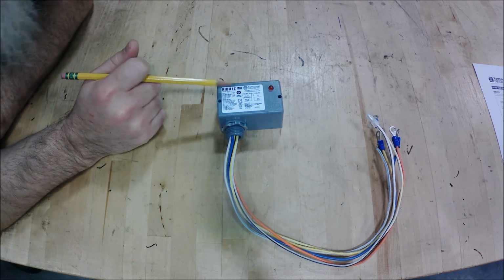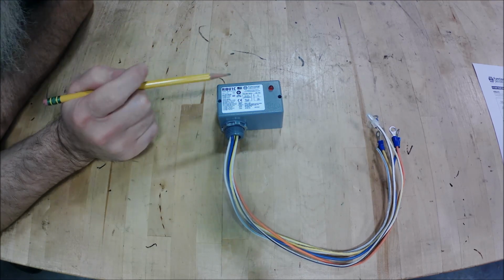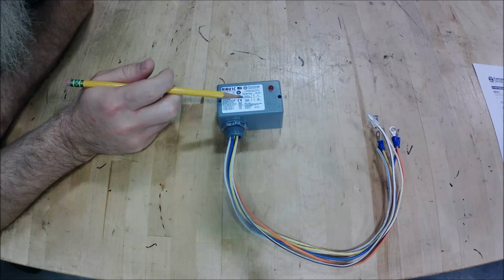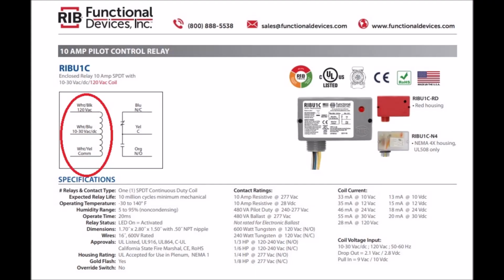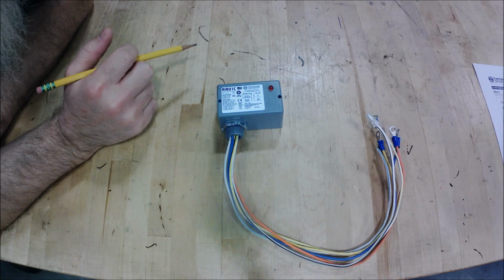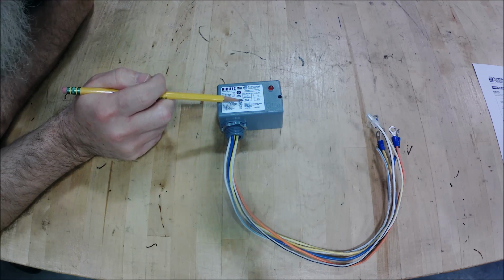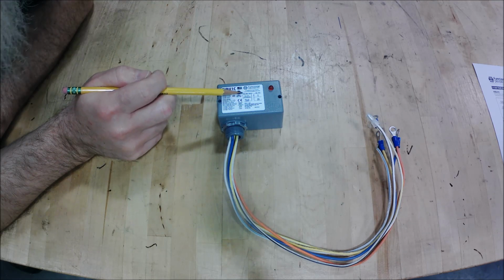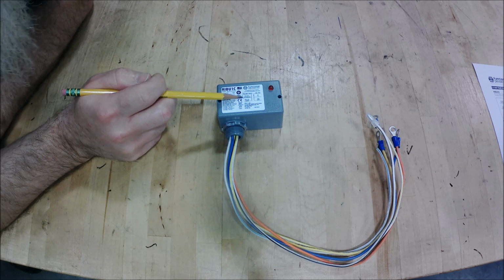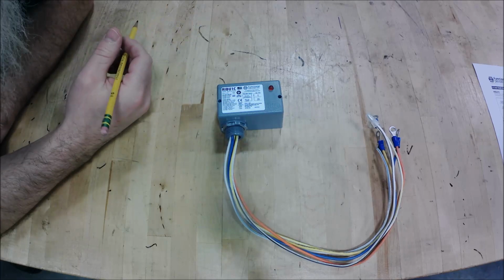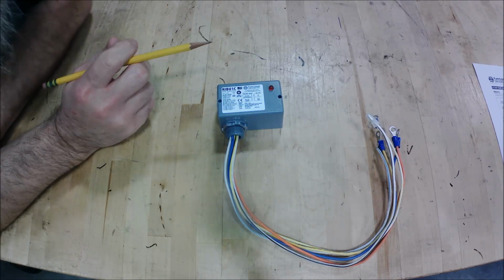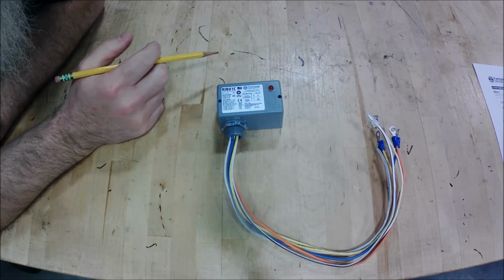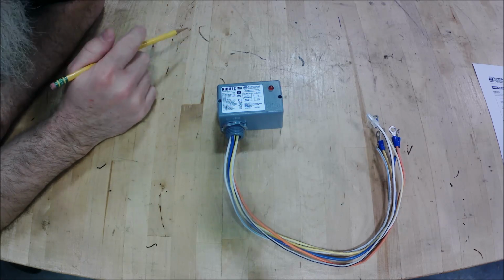So on top of it, and I'll throw up the spec sheet real quick, you've got your coil voltages listed. What we can do here, we have a common connection, and we have 120 volts AC to the coil, or you can use 10 to 30 volts AC or DC on here, and that falls in line with our residential style 24 volt control system. So I'm going to use it in our air handler that we've done before.